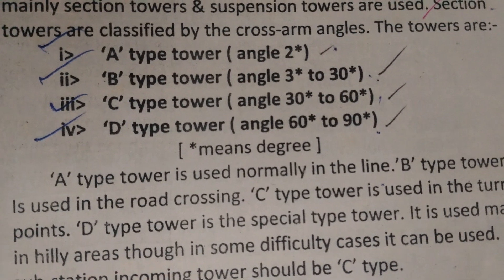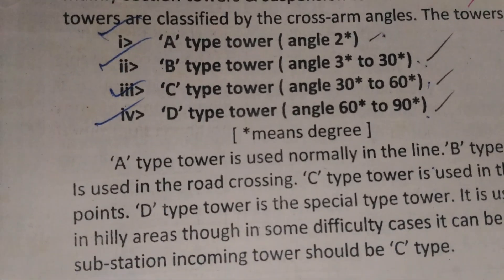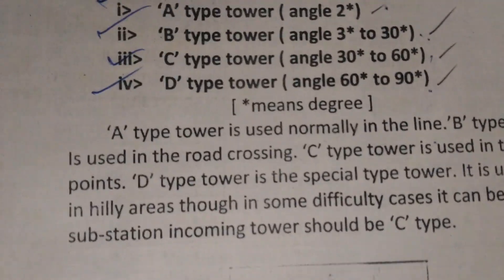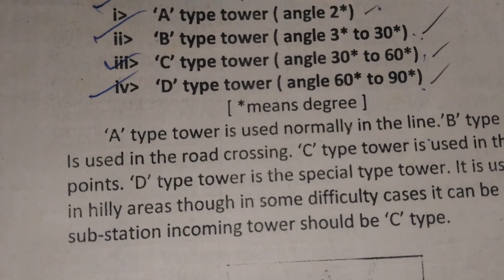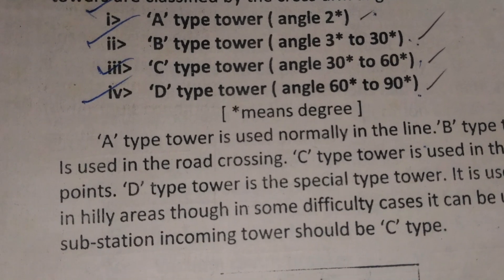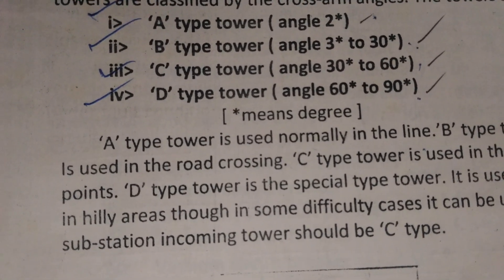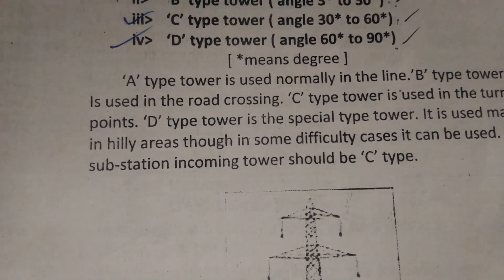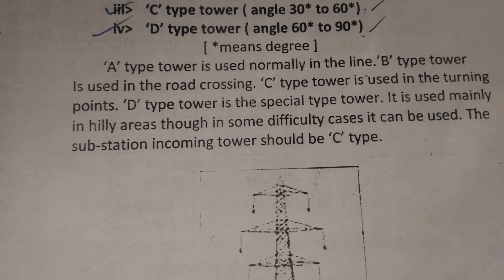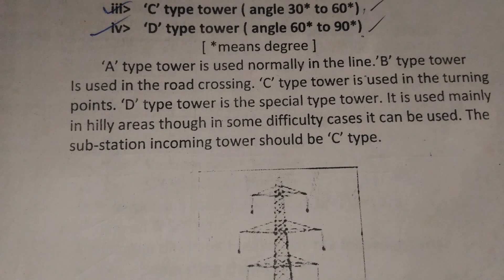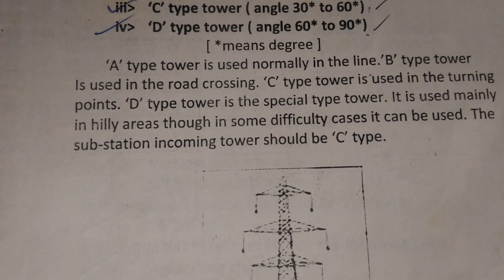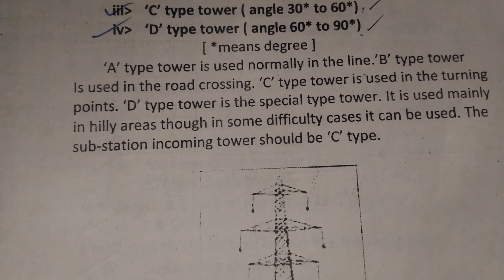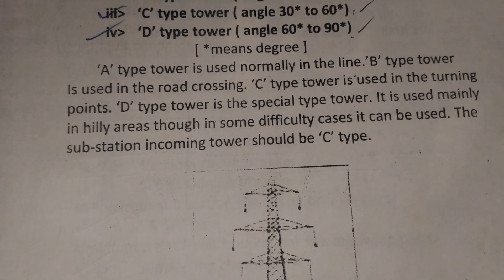Section towers are classified by the cross arm angle. A-type tower has an angle of 2 degrees. B-type tower has an angle of 3 to 30 degrees. C-type tower is 30 to 60 degrees. D-type tower is 60 to 90 degrees. A-type tower is used normally in the line. B-type is used in road crossings. C-type is used at turning points. D-type is a special tower mainly used in hilly areas, and in some difficult cases it is used for substation incoming towers, which should be C-type.